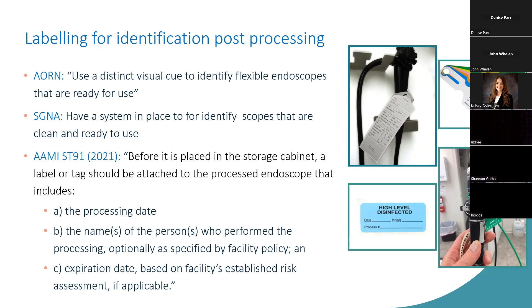At the facility I came from, we standardized and educated to a green zip tie, like you see in the lower right picture. We made sure anybody that touched the process understood that green means clean and not to use a scope that didn't have the green zip tie in place. And we also created an expectation that the tie was put on so that it was in the way for the practitioner. They had to remove it. So it was in the way. And if it wasn't there, no questions asked, the scope wasn't used. Besides declaring post-HLD status, the physical identifier should include the processing date, the name or initials of the person who performed the processing, and the facility-determined expiration date.